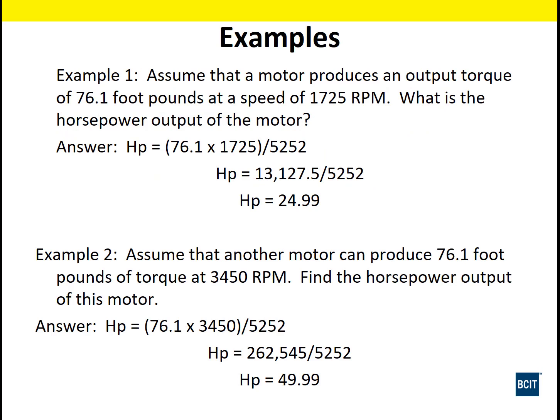So for an example here, let's have a look. If we need 76.1 foot-pounds of torque at 1725 RPM, we're going to need about a 25 horsepower motor. Now typically you don't size it to exactly what you need. They're going to size these a little bigger, so that might end up being a 30 horse. And then again at 3450 RPM, for the same amount of torque, we're going to need a 50 horsepower.